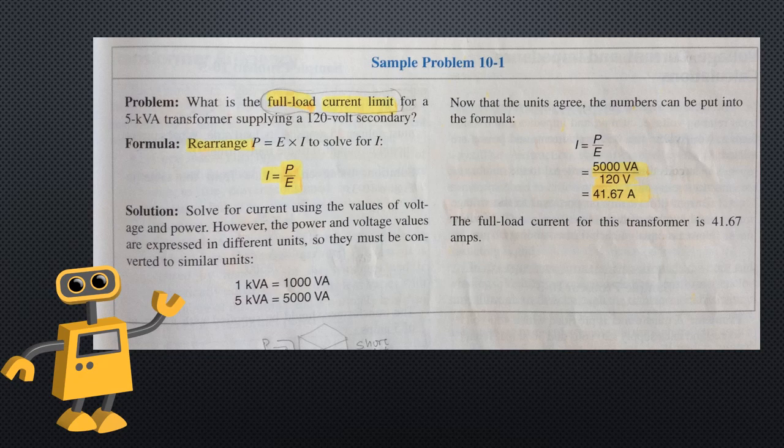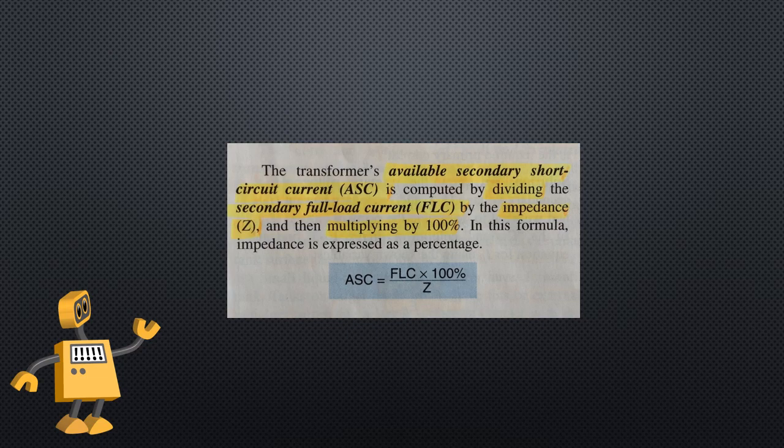Impedance. The impedance of a transformer is an indication of the short circuit current delivered when a direct short is placed across the secondary terminals. The impedance factor is listed as a percentage on the transformer nameplate and is used in sizing overcurrent protective devices. Take note of this—it is very important.